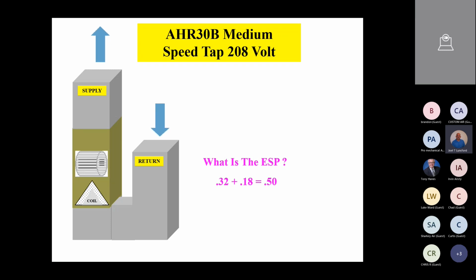Let me stress that again. You just add up the whole numbers. So it's 0.32 inches of static on the supply point. It's a negative 0.18 static on the return. You just add those up for a total static pressure. In other words, it's the amount of total pressure that fan is sucking and blowing against the ductwork and all the registers and the filters and stuff like that, for a total of 0.5.